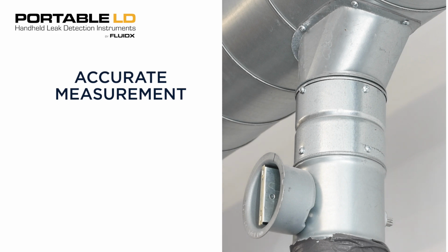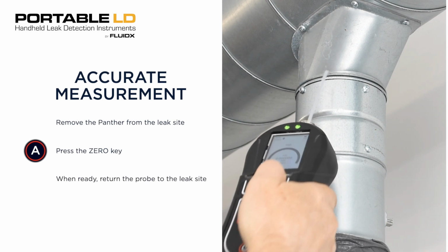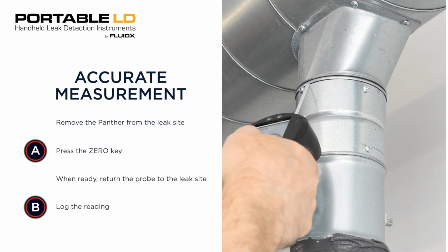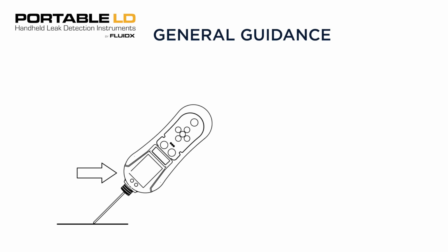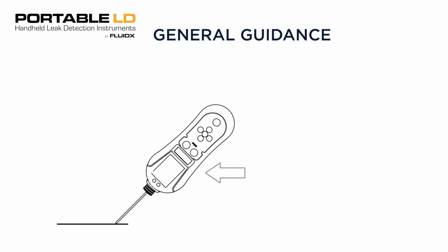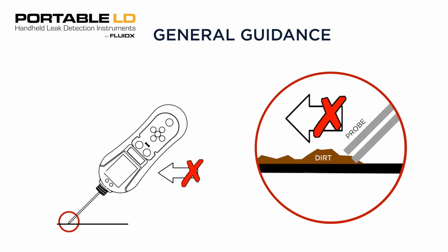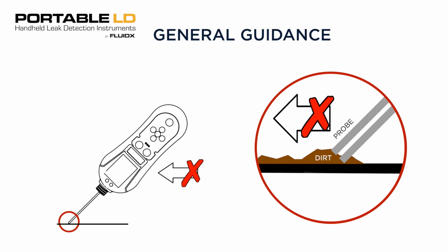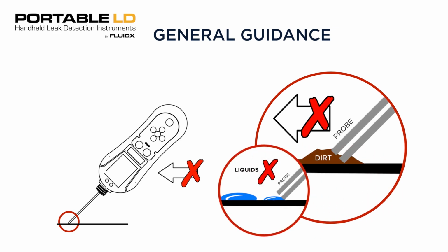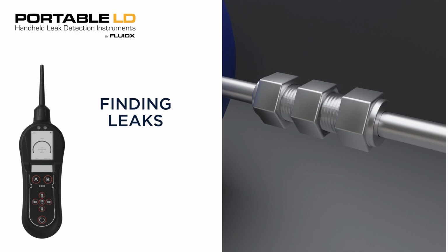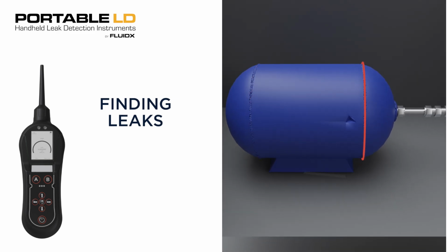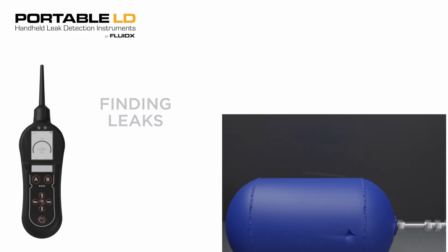For an accurate measurement, remove the Panther from the leak site and press the 0 button. Once ready, return the probe to the leak site and log the reading. Always drag the probe, never push it, as dirt can cause blockages. Also, avoid contact with liquids for the same reason. While gas leaks can technically occur anywhere, they are most commonly found at pipe joints, welded seams, or damaged surfaces.